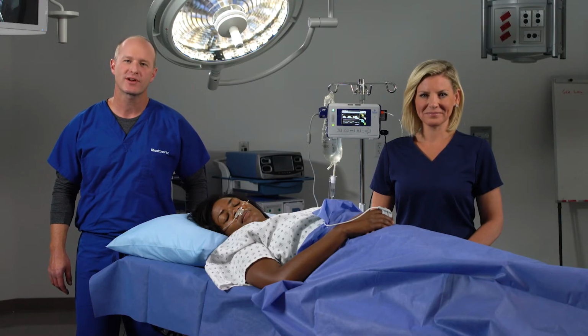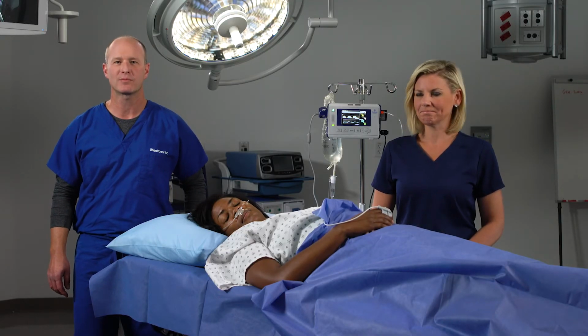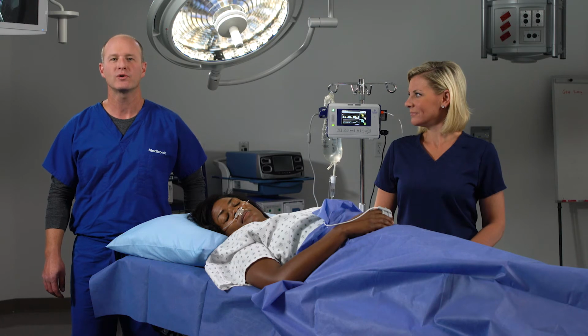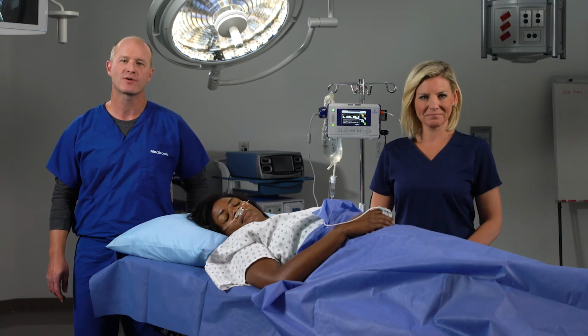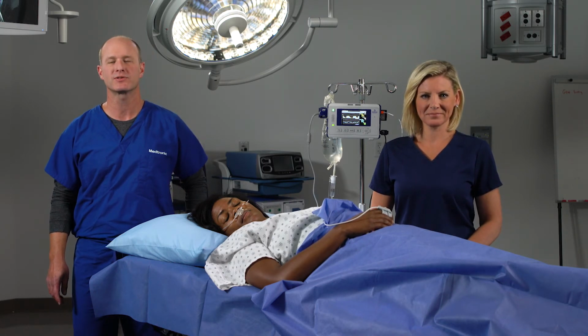Between patients, dispose of the sampling line and disinfect the monitor per the operator's manual. The Capnostream 35 monitor does not require calibration in between patients, only once every 4,000 hours of operation or once a year, whichever comes first. This concludes our Buttonology review.